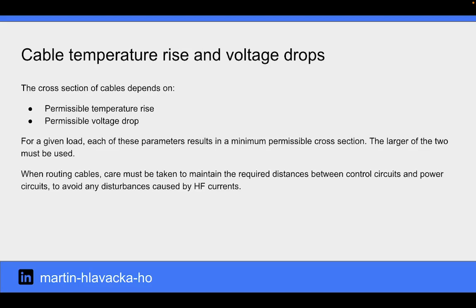The cross-section of cable depends on permissible temperature rise and permissible voltage drop. For a given load, each of these parameters results in a minimum permissible cross-section. The larger of the two must be used. When routing cables, care must be taken to maintain the required distances between control circuits and power circuits to avoid any disturbances caused by high-frequency currents.